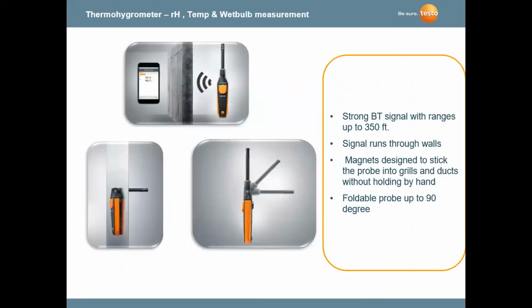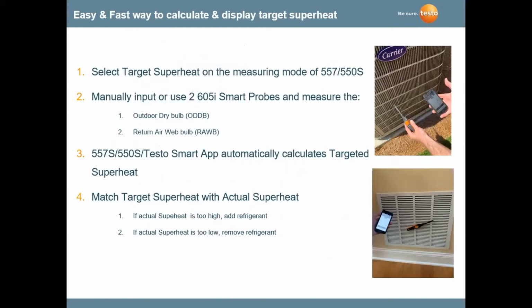Today, again, it's back to this digital relative humidity temperature instrument, where we are taking the outdoor dry bulb temperature and the return air wet bulb temperature inside the room, and we're getting the calculated targeted superheat. It's done very quickly on these instruments, and you're matching the actual superheat to the targeted superheat by using additional smart probes, 605i smart probes. Or you can just insert the outdoor dry bulb and the return air wet bulb manually as well.